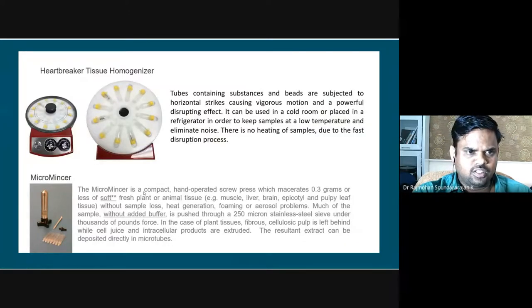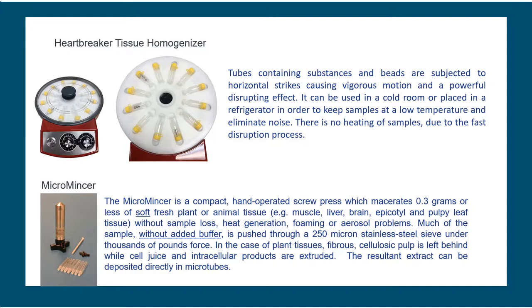The Heartbreaker tissue homogenizer is a compact, hand-operated, screw-press type cell disrupter. It can be used to separate out cells and organelles from fresh plant and animal tissues like muscle, liver, brain, and pulpy leaf tissues. There is no sample loss, no heat generation, no foaming or aerosol problems. The sample is pushed through a 250-micron stainless steel sieve under thousands of pounds of force. For plant tissues, the fibrous cellulosic pulp is left behind while cell juice and intracellular products are extruded. The resultant extract can be deposited directly into microtubes.